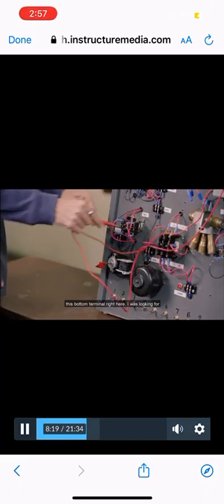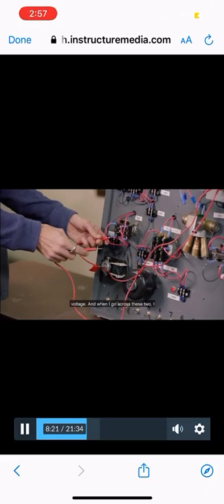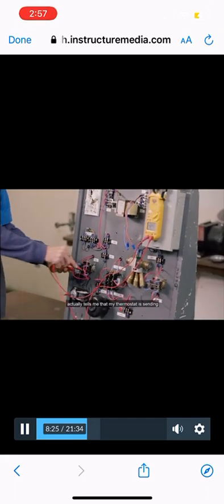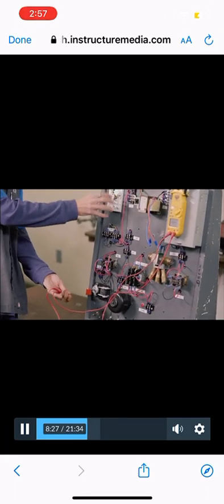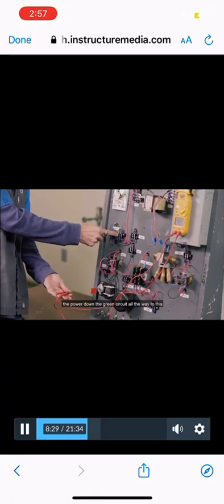So by doing this and going across this bottom terminal right here, I was looking for voltage. And when I go across these two, I see voltage on there, which is a good sign. That actually tells me that my thermostat is sending the power down the green circuit all the way to this relay. With power on the coil here, I want to go up to the top. This is my switch up here. This is actually what's going to turn this motor on.